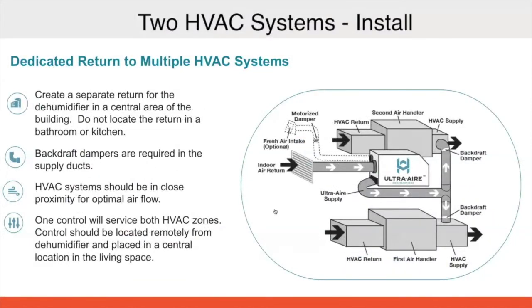We also have a two HVAC systems install. Just got this question yesterday if this is a possibility. It absolutely is. So we can use one dehumidifier. Typically we see this in new construction tied to two systems, and then we're going to use a controller in a centralized area that's going to read the RH and deliver that dry air to both areas.